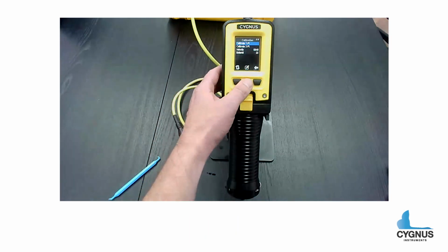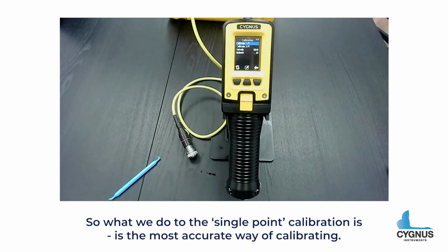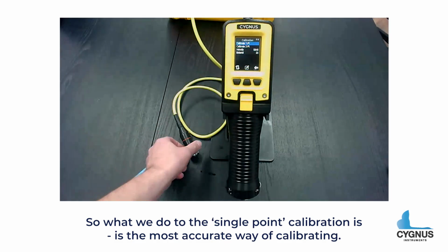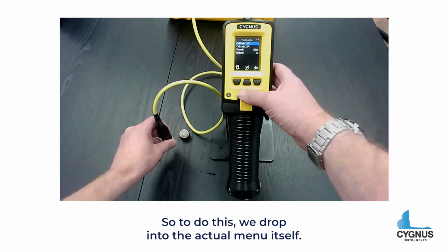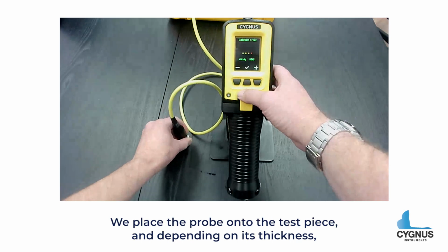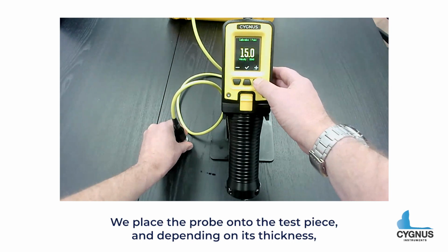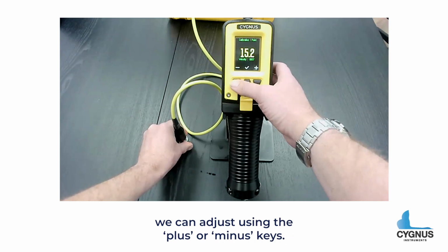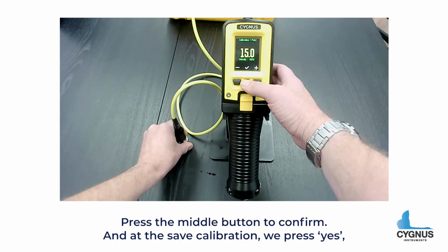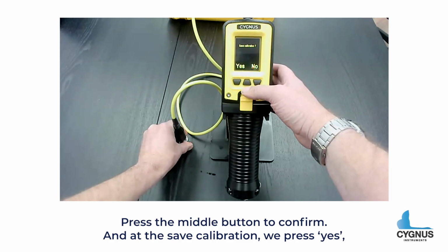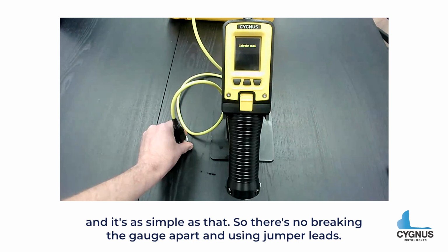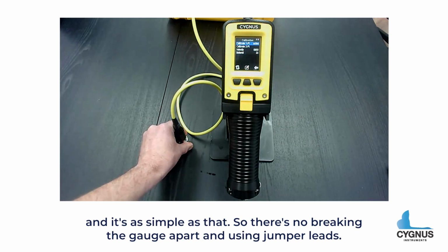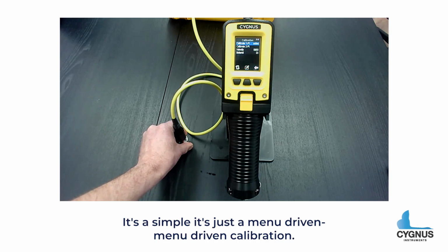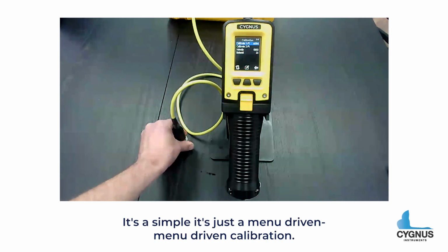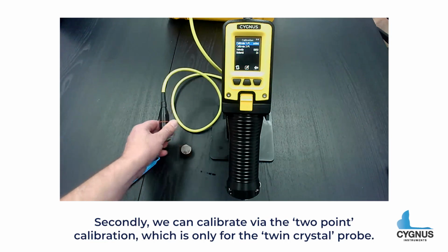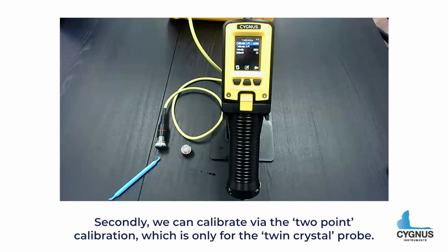It's just another menu. The single point calibration is the most accurate way of calibrating. To do this, we drop into the actual menu itself. We place the probe onto the test piece, and depending on its thickness, we can adjust using the plus and minus keys. Press the middle button to confirm, and then to save the calibration, we press yes. And it's as simple as that. So there's no breaking the gauge apart and using jumper leads. It's just a menu-driven calibration.